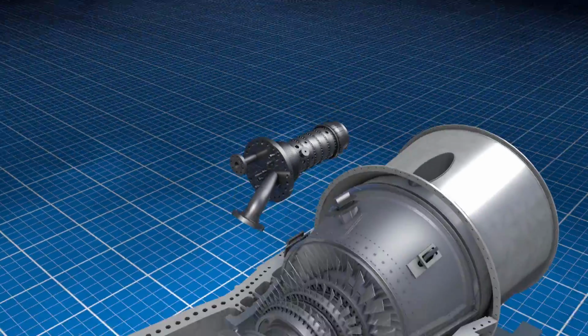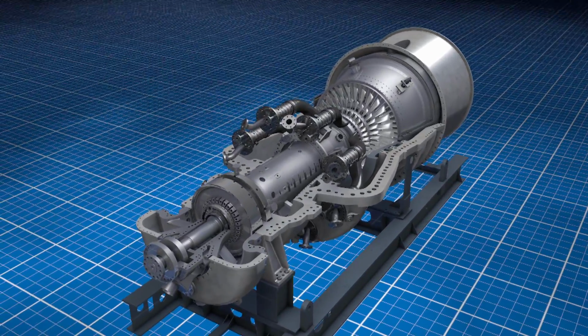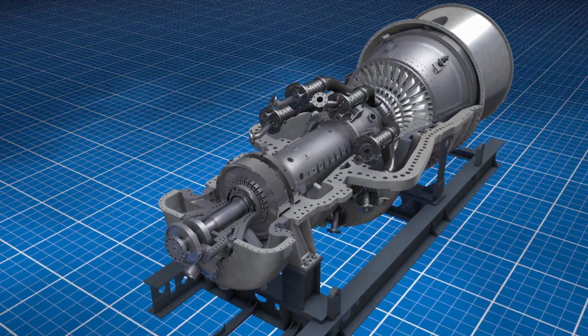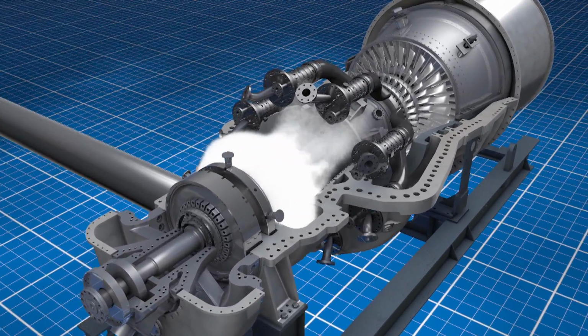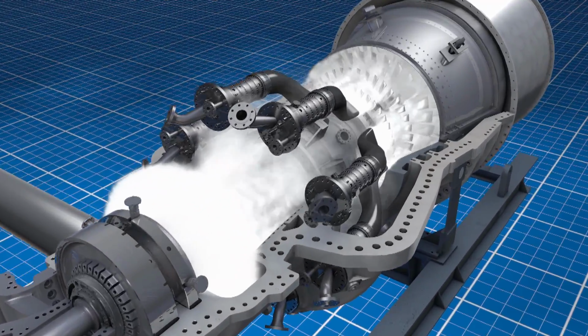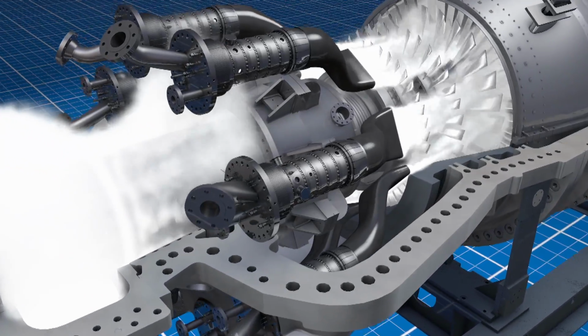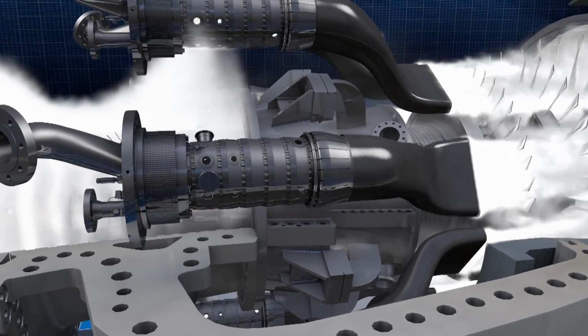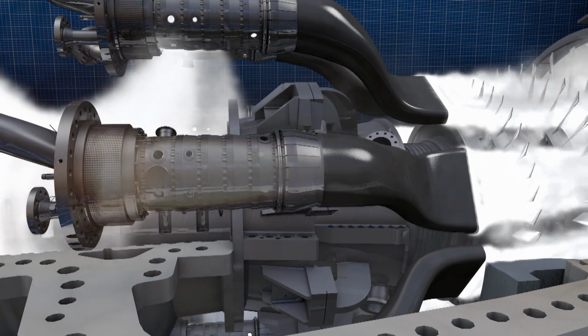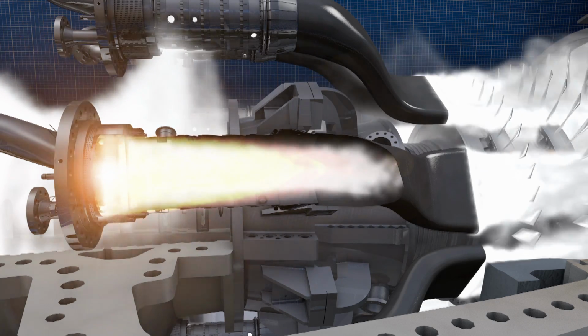Having the drive gas enter the turbine at the required design pressure eliminates the need for the traditional compressor. Steam is injected into the OFT900 and passes along the shaft into a plenum before entering the reheaters. While maintaining the pressure of the drive gas, the reheaters boost temperatures to the ideal inlet conditions for the OFT900 expander section, where roughly 150 megawatts of power is generated.